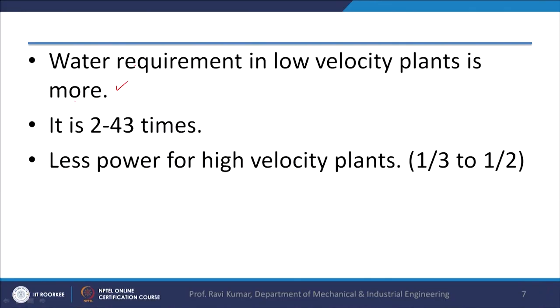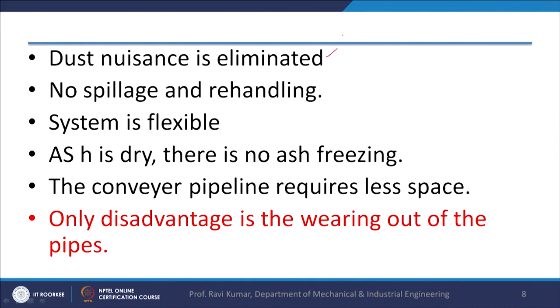Water requirement in a low velocity plant is higher — 2 to 3 times that required for mechanical handling. For a high velocity plant, less power is required, approximately 1/3 to 1/2. In the air (pneumatic) system, dust nuisance is eliminated, no spillage, the system is flexible, ash is dry, and there is no ash freezing. The conveyor piping requires less space since only air and ash need to be handled.